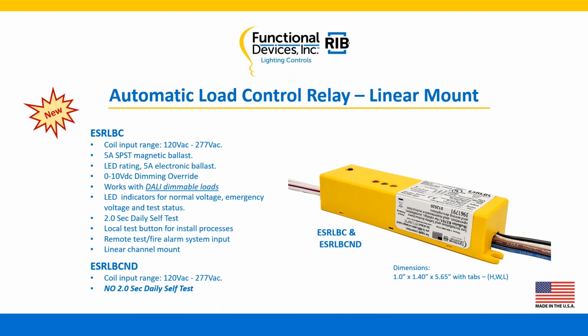It's a 5 amp single pole, single throw magnetic ballast. You've got to remember it's at the fixture level, so you don't really need a hefty relay there. It does have 5 amp electronic ballast ratings. We give you the 0 through 10 volt dimming override.